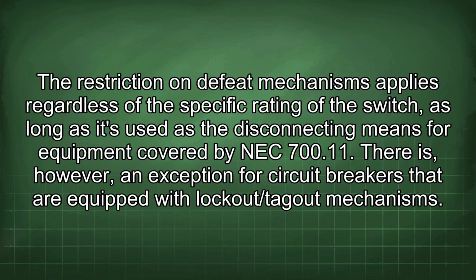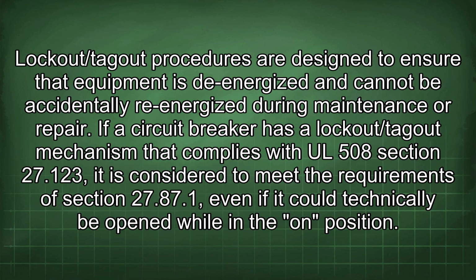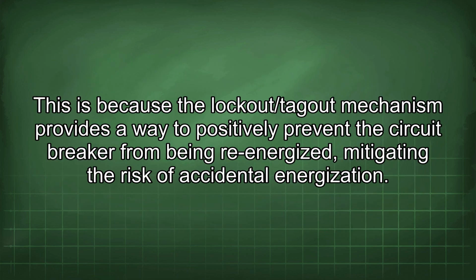There is, however, an exception for circuit breakers that are equipped with lockout/tagout mechanisms. Lockout/tagout procedures are designed to ensure that equipment is de-energized and cannot be accidentally re-energized during maintenance or repair. If a circuit breaker has a lockout/tagout mechanism that complies with UL 508 Section 27.123, it is considered to meet the requirements of Section 27.87(1), even if it could technically be opened while in the on position.